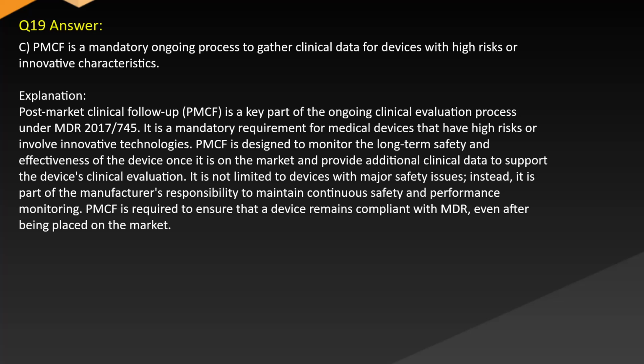Explanation: Post-market clinical follow-up, PMCF, is a key part of the ongoing clinical evaluation process under MDR 2017-745. It is a mandatory requirement for medical devices that have high risks or involve innovative technologies. PMCF is designed to monitor the long-term safety and effectiveness of the device once it is on the market and provide additional clinical data to support the device's clinical evaluation. It is not limited to devices with major safety issues. Instead, it is part of the manufacturer's responsibility to maintain continuous safety and performance monitoring. PMCF is required to ensure that the device remains compliant with MDR even after being placed on the market.